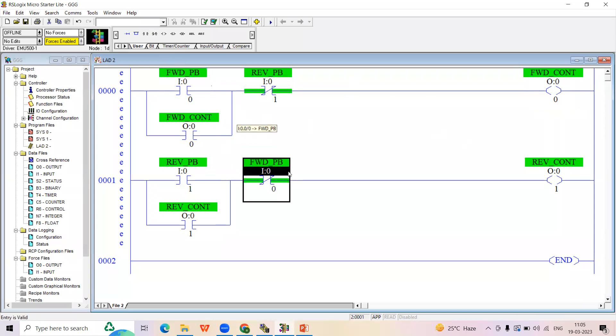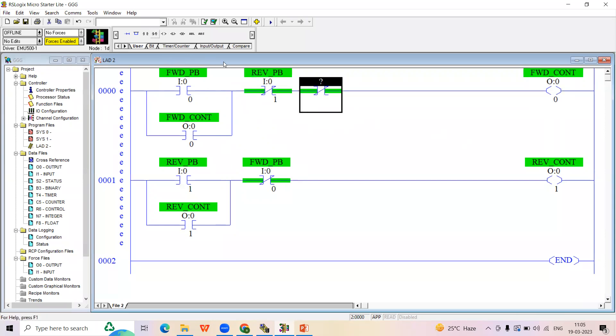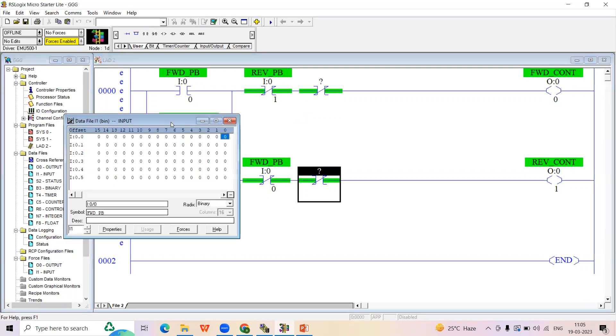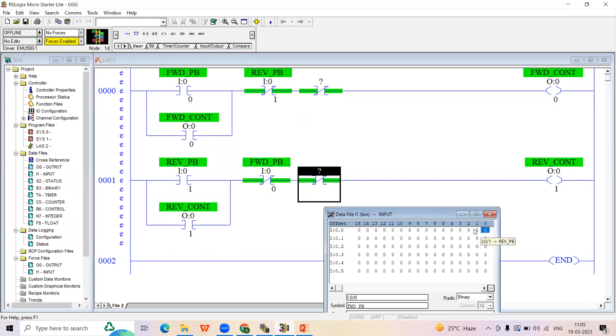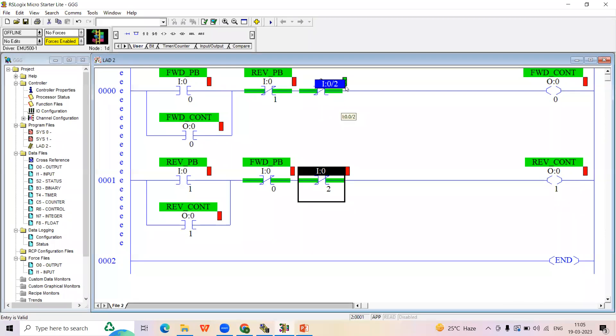When the forward contactor should be stopped — that is, when the reverse push button is pressed — drag the reverse push button address to an NC contact and place it in series on the forward rung. Similarly, when the forward push button is pressed and the reverse contactor should be stopped, drag the forward push button address to an NC contact on the reverse rung. Also, add the stop push button as a third NC contact in series on both rungs, using the third input address, since stop is common to both forward and reverse.